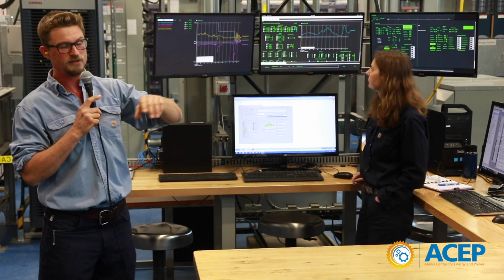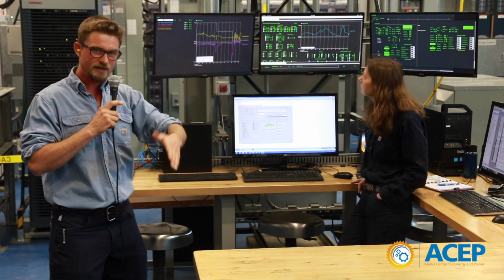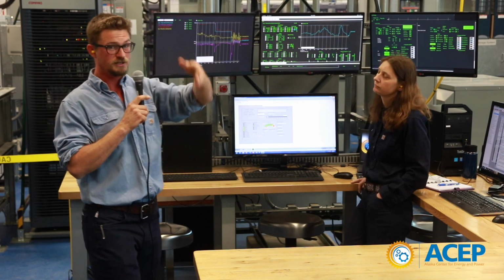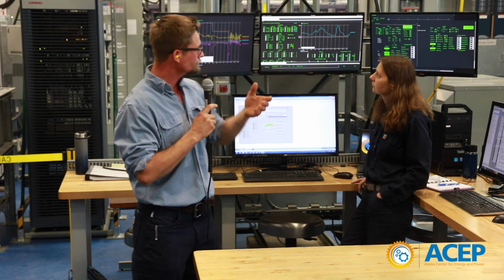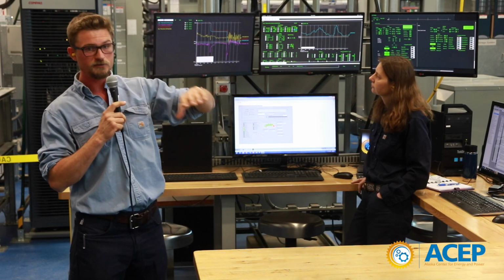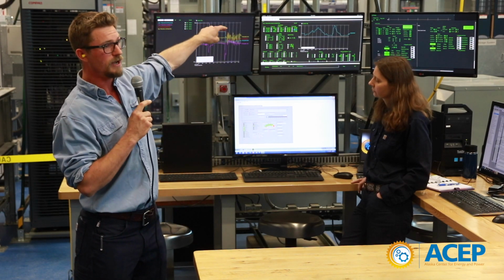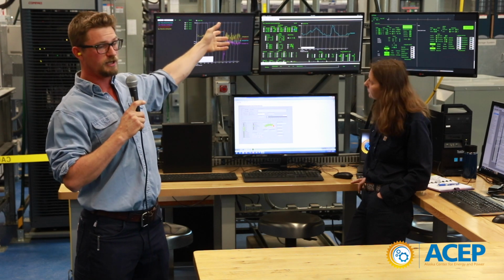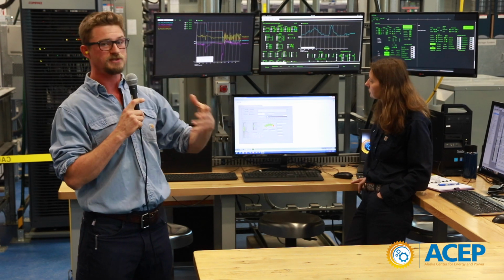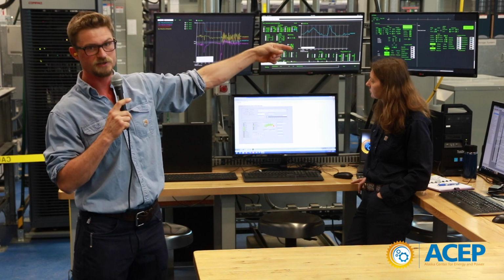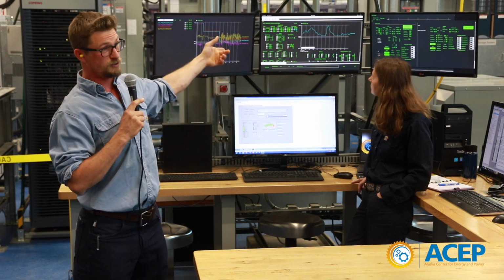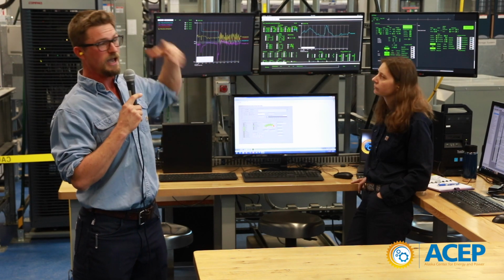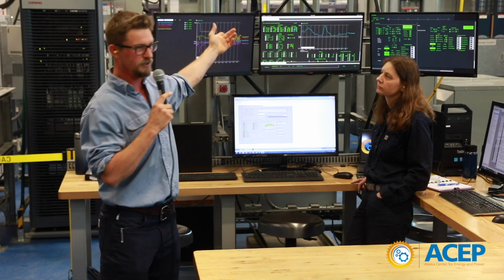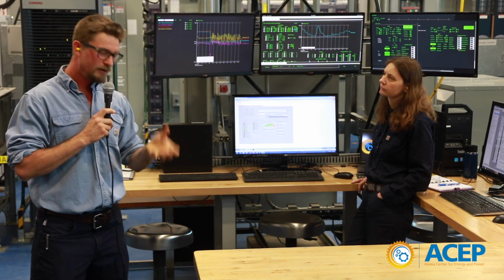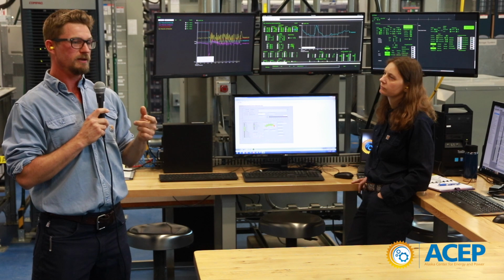Remember how we said the generator makes that frequency, sets the grid voltage and frequency that everything else follows? This inverter can do that. It can supply a lot of the same services the generator supplies, but it doesn't consume fuel. It takes energy stored in the battery.